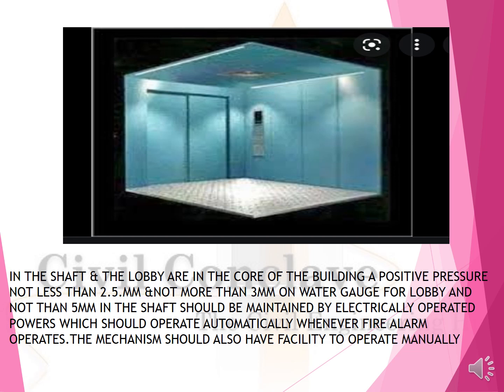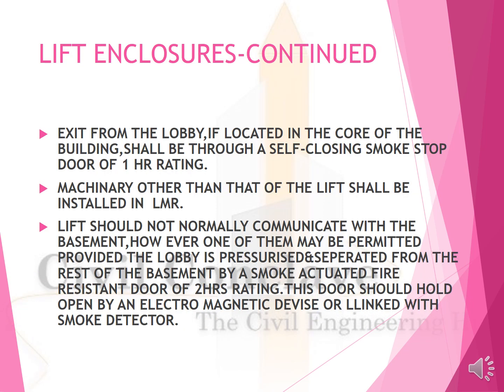In the shaft and the lobby, in the core of the building, a positive pressure of not less than 2.5 mm and not more than 3 mm on the water gauge for the lobby, and not less than 5 mm in the shaft, should be maintained by electrically operated blowers, which should automatically operate when the fire alarm operates. Lift enclosure. Exit from the lobby located in the building shall be through a self-closing smoke door of 1 hour rating. Machineries other than the lift shall be installed in the LMR.